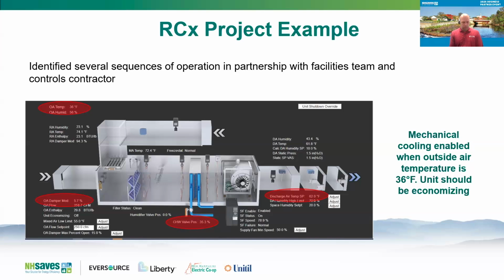One thing that's really important with economizers too is making sure that the outside air damper actuator actually works. I can't tell you how many times you open up an air handler and the linkage is just dangling in the plenum because it's not hooked up or the actuator just doesn't work because it's so old. So making sure those end devices are functioning properly is really important. This is just one of the examples from this project.